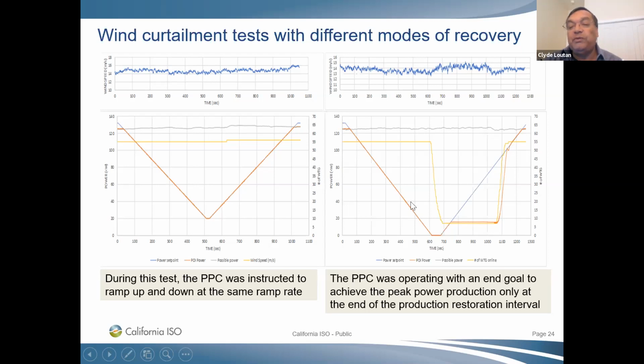So if you see the response here, we backed this unit off, came back up a little, but then all of a sudden at this point, right just before 11 o'clock, we said, hey, give us everything you got. And you can see how quick this plant was able to respond. So it ignored the ramp rate and just gave you full capability. So if you need wind plants to operate quick, they can do that. If you need them to operate at a ramp rate, they can also do that.